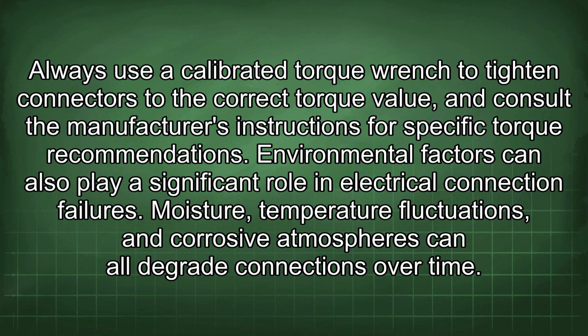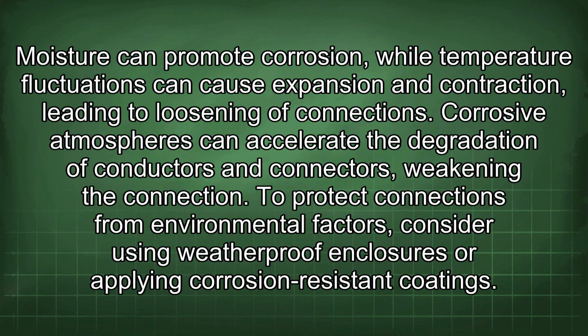specific torque recommendations. Environmental factors can also play a significant role in electrical connection failures. Moisture, temperature fluctuations, and corrosive atmospheres can all degrade connections over time. Moisture can promote corrosion, while temperature fluctuations can cause expansion and contraction, leading to loosening of connections. Corrosive atmospheres can accelerate the degradation of conductors and connectors, weakening the connection. To protect connections from environmental factors, consider using weatherproof enclosures or applying corrosion-resistant coatings.